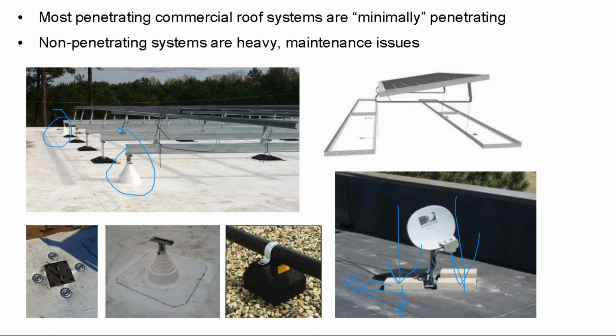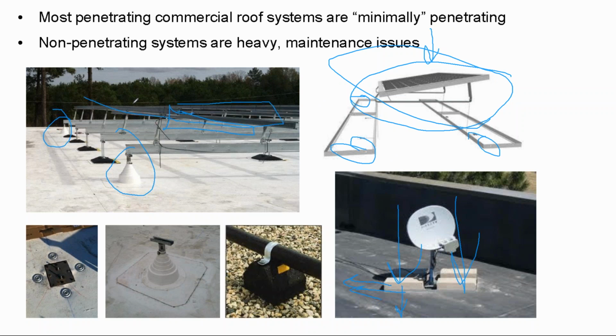And consider adding anchor points to the array, even if you're using a system like this where it's the common and the cheap system where the array is sitting right on the roof deck. Even in a system like this, anchoring the corners of the ballast system to the roof, anchoring the corners of the large subarray is all you need to substantially reduce the concrete that is filled in to the ballast pans.